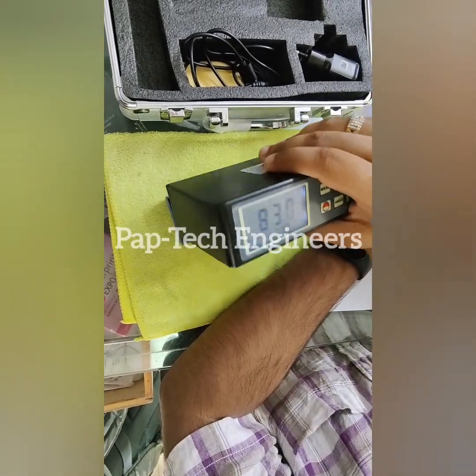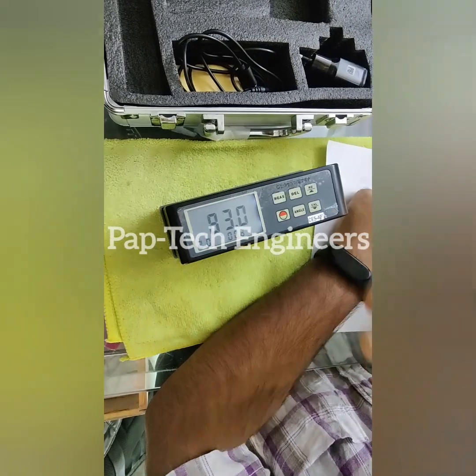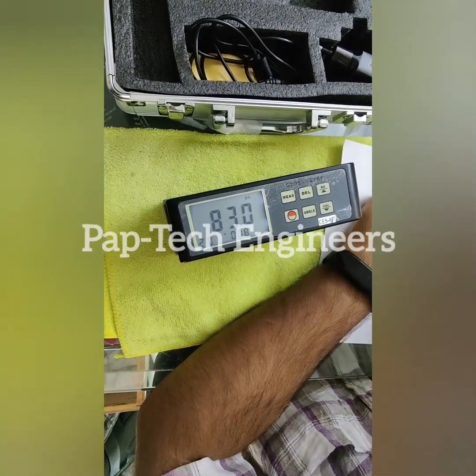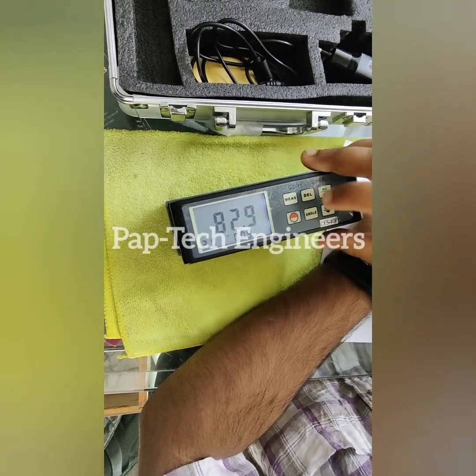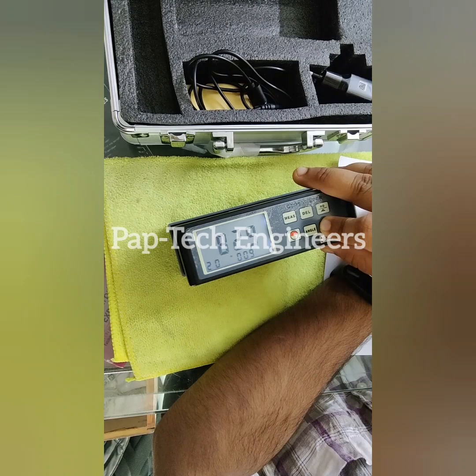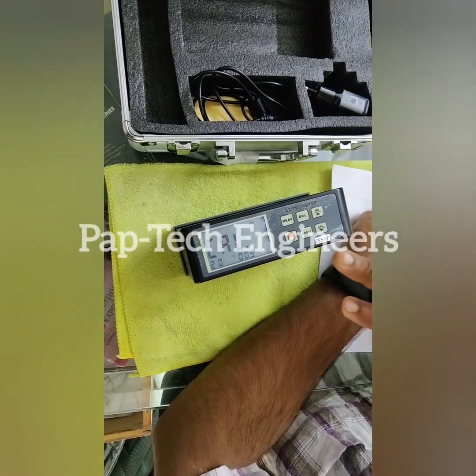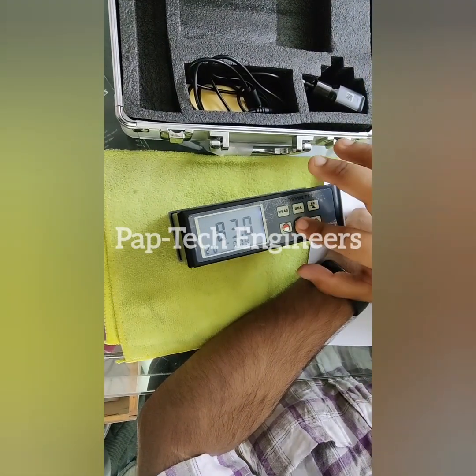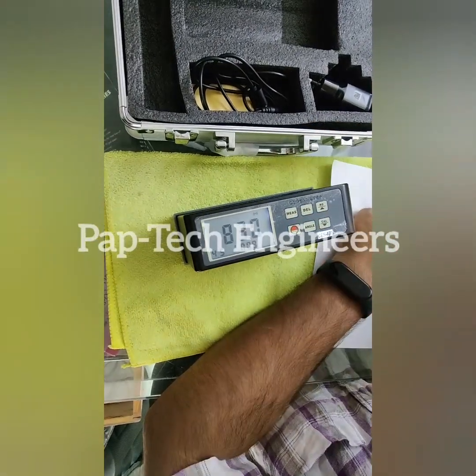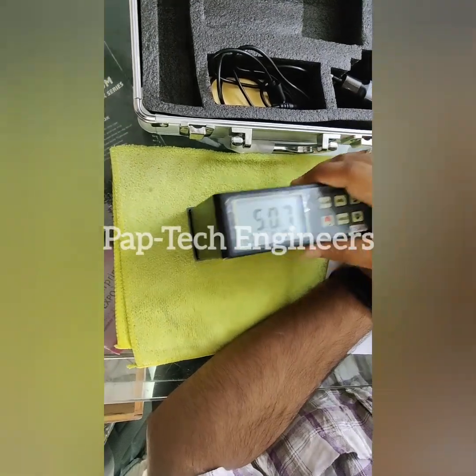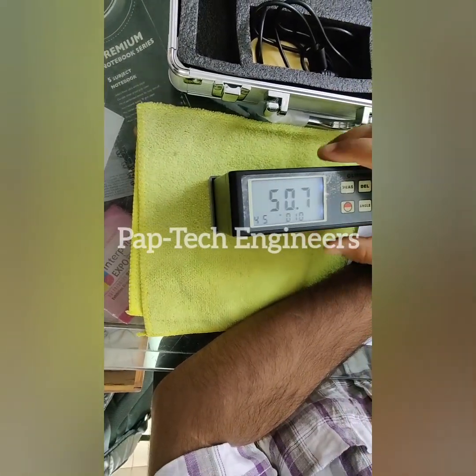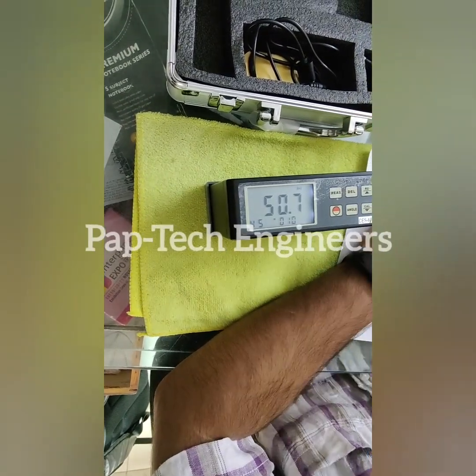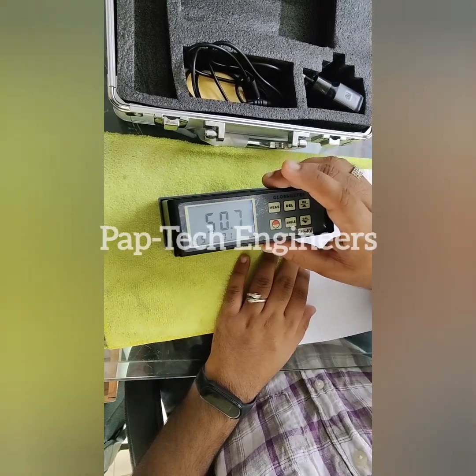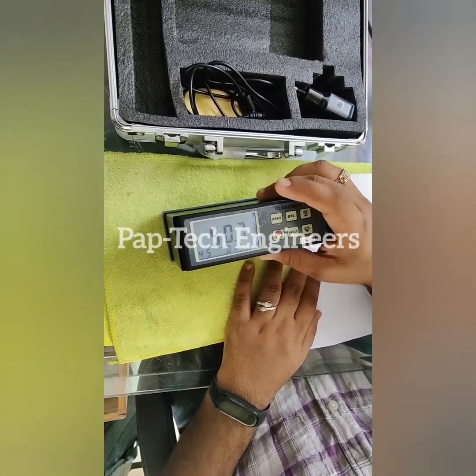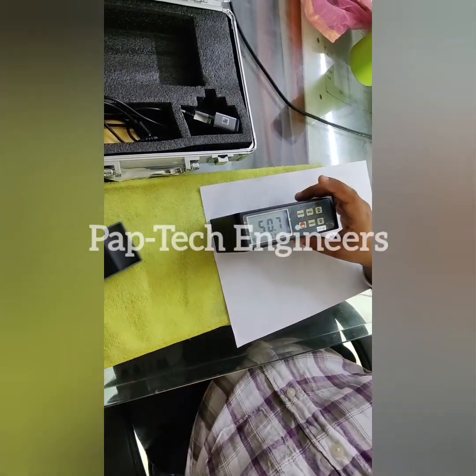So now it's coming 83. So again we take its reading first, and then if it is not calibrated, we'll calibrate this machine. It's coming 82.9. Let's calibrate again. We only have to use the calibration button if the machine is showing out of calibration. That's why we have given you this calibration standard. Let's check at the other angle, 45 degree. This measurement is coming 50.7 and it should come 50.5. It means this is already calibrated. Again we can check with the measurement button. Okay, there can be an error of 1.5 to 2 gloss unit, that is possible, but not more than that.